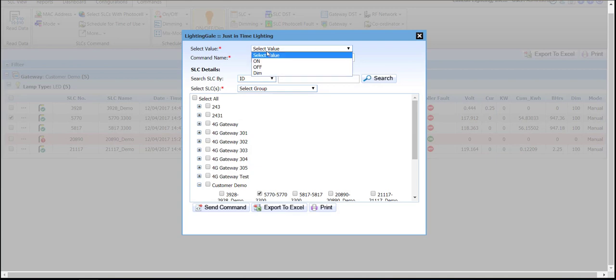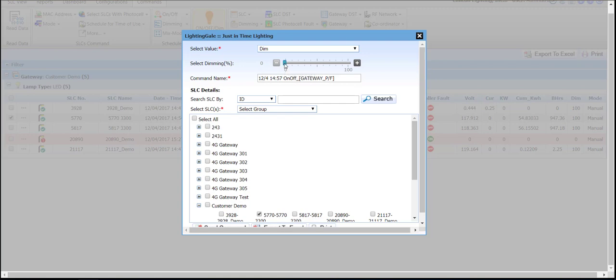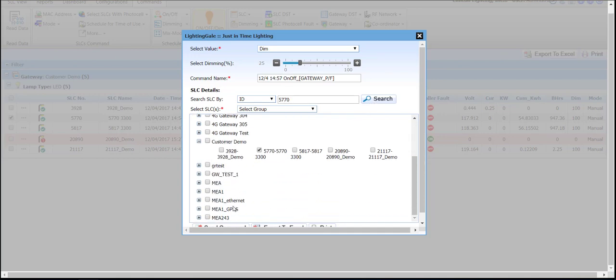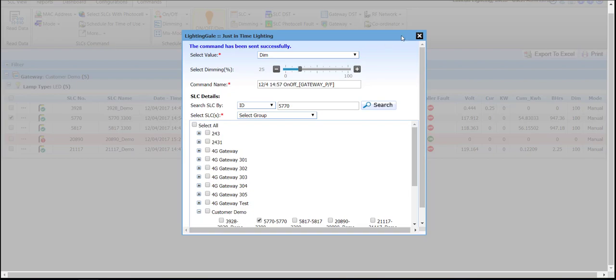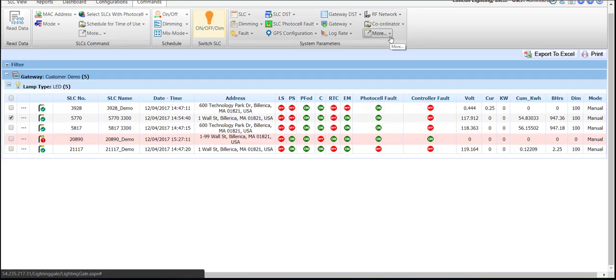We'll select the value, and in this instance I will select dim. To select the dimming percentage applied, we will just click and drag this drag bar here — say 25. I do want to point out that 25 in this case is the amount of dimming applied, meaning the light will be at 75% output. So we'll search for the SLC number as noted, and I'll scroll down and click Send Command. If you happen to be sitting near the lights, you will be able to watch the fixture turn on, off, or dim right in front of you, verifying the control of that fixture.